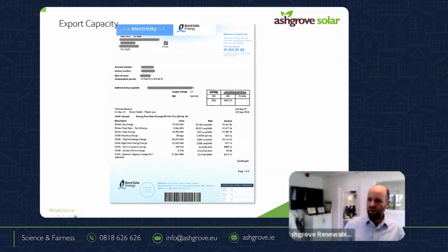In terms of export capacity, we spoke earlier about the MIC, maximum import capacity, and the MEC, maximum export capacity. The MIC is a good reference point for what we're likely to get approval for to go back out onto the grid. So if you have an MIC of 50 kilowatts, there's no real point, unless we have a conversation with ESB, in putting in an application for a 200 kilowatt inverter. You'd have to increase your MEC significantly when you're only consuming 50 kilowatts in terms of import capacity.